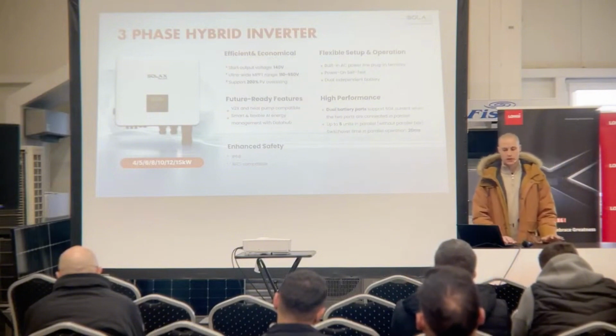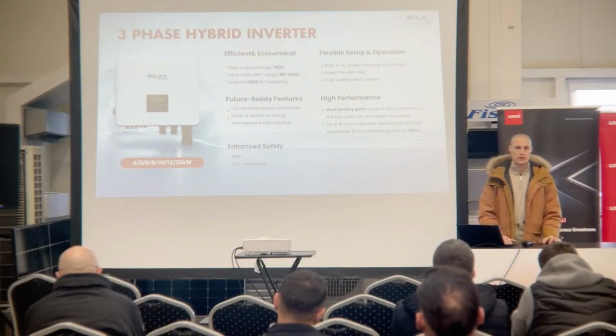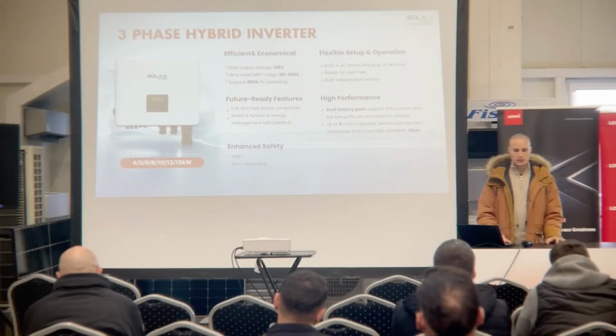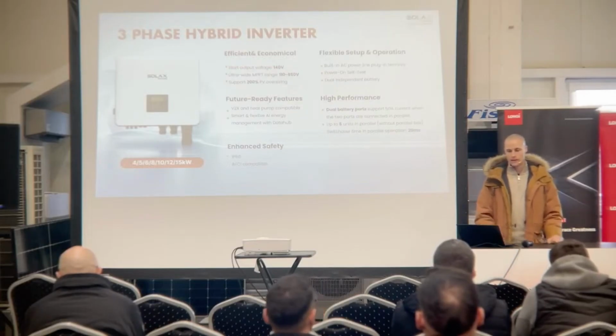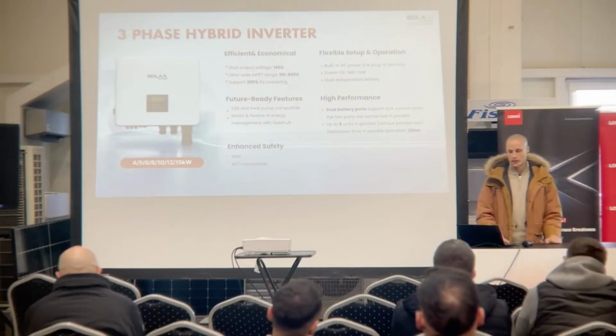That's really good for residential solutions because it's not rare that you have 3 different angles of the roof that you have to install panels onto, and with these 3 MPPTs you can easily harvest the energy without using optimizers. Also, you can use 200% oversizing on the PV side without optimizers, so a 10 kilowatt inverter can accept 20 kilowatt of PV panels.